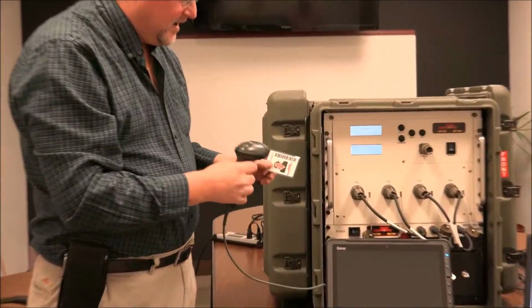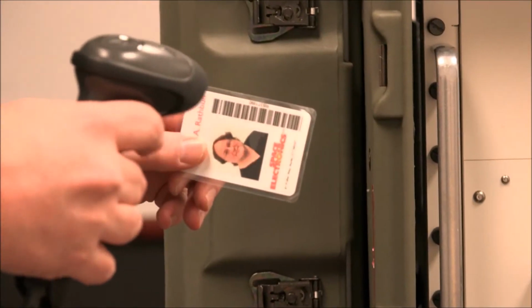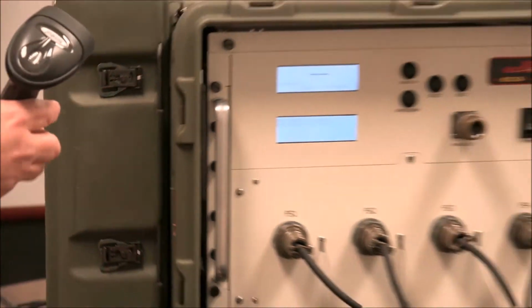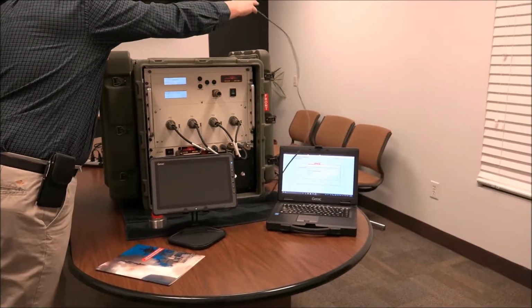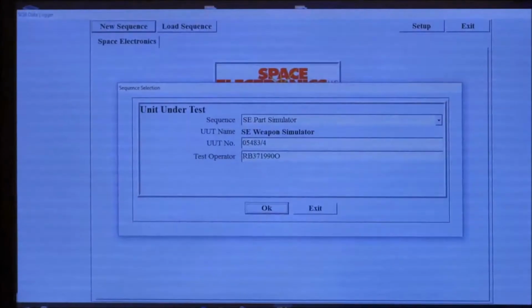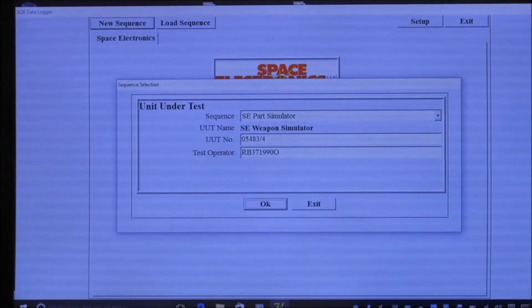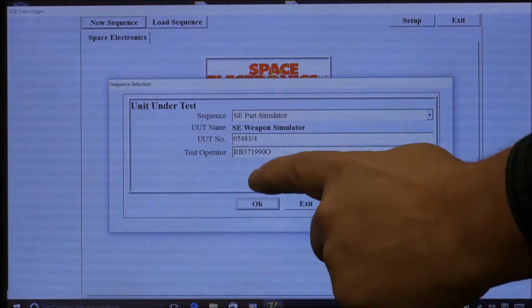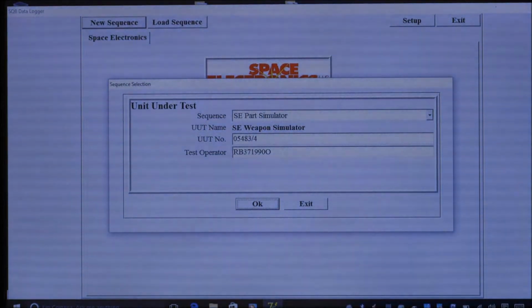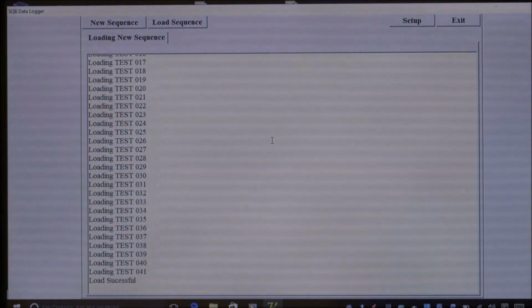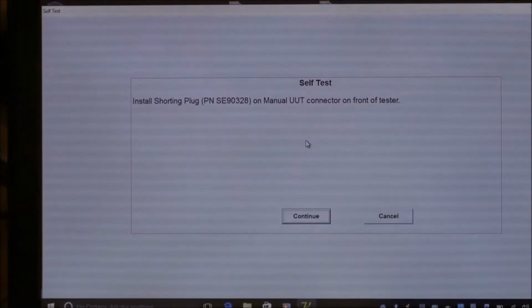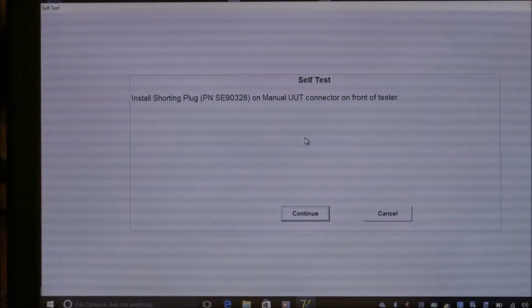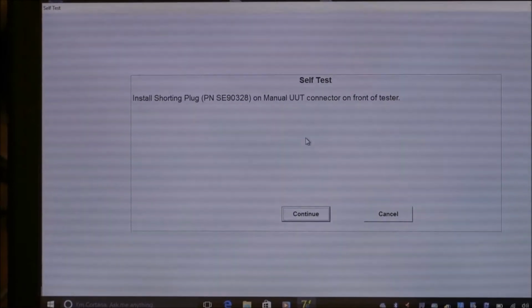I'll take my ID off, scan it, and it automatically loads that data. So now that information is going to go in my computer and it's going to be stored with my test. It's automatically highlighted the OK button, so I really only have to hit continue. It's now loaded the sequence, and it's going to start by making sure I've got everything connected.